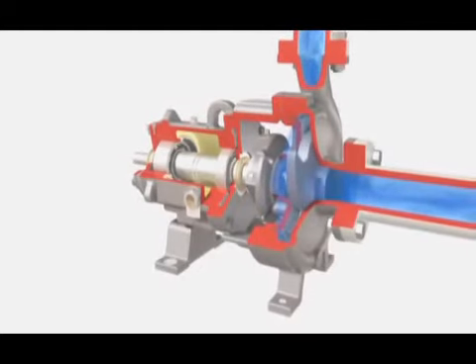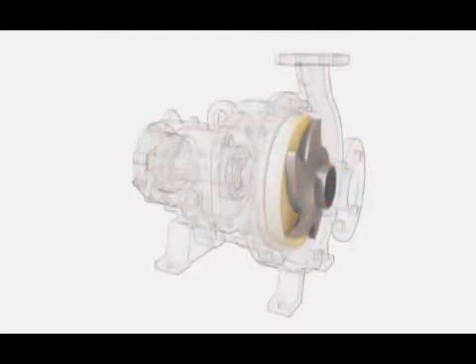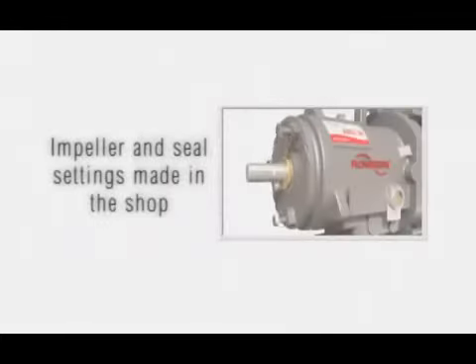Because the critical running clearance is set off the rear cover and not the casing, several advantages are realized. Impeller and mechanical seal settings can be made in the shop, on the bench, instead of under adverse field conditions.